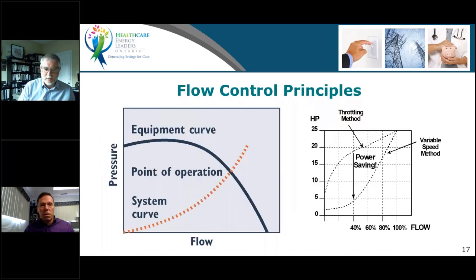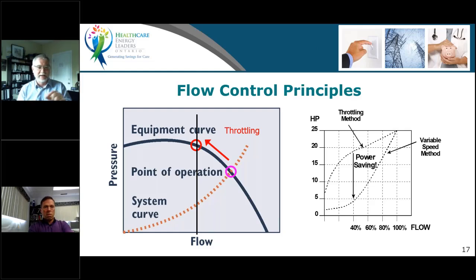So when it comes to actually applying flow control to a system, we have to do it with respect to what's happening underneath. So it's not just a matter of whipping a variable speed drive on a motor driving a pump and okay, we're all good here. We need to understand what we're trying to achieve. So ultimately, we might be operating at this point with this flow on this particular pump, and we want to reduce the flow. So maybe we want to reduce the flow by 1/3. So we close that valve and we throttle it. Or maybe this happens accidentally. One way or the other, if we restrict that pump, no matter how we restrict it, we're going to move up that pump curve. So we move to that throttle point.